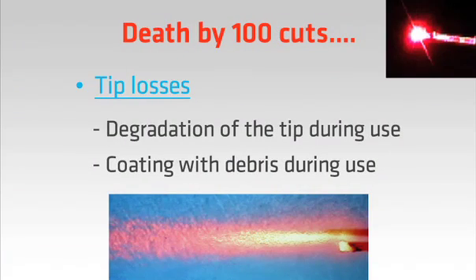As we are using the tip during surgery its performance becomes affected by heat-induced degradation. This is why the tips are designed as disposable items for single procedure use. A damaged tip will show a bizarre pattern from the red aiming beam. During contact procedures like surgery and periodontal disinfection, sticky strands of tissue will coat onto the sides of the tip and onto the end. This material needs to be wiped off so the emission of laser energy is not affected. At the end of the procedure just throw the tips away. Don't try to steam sterilize them or they will just melt.